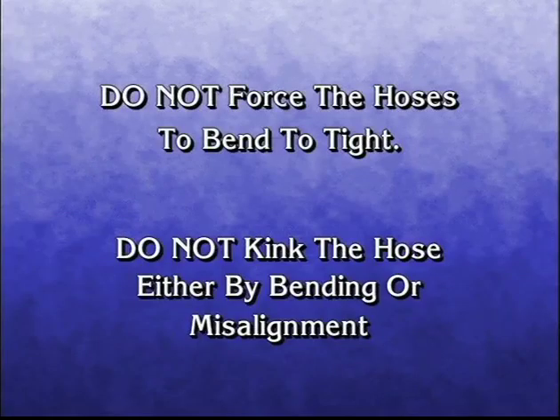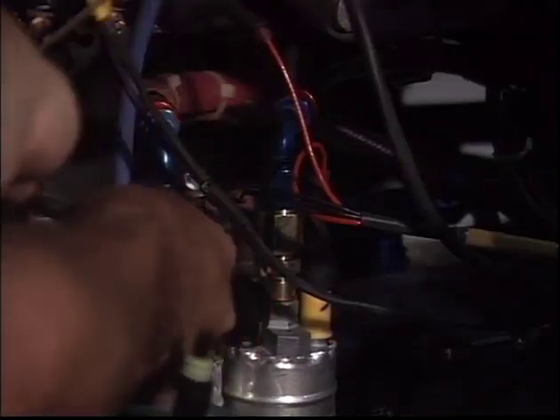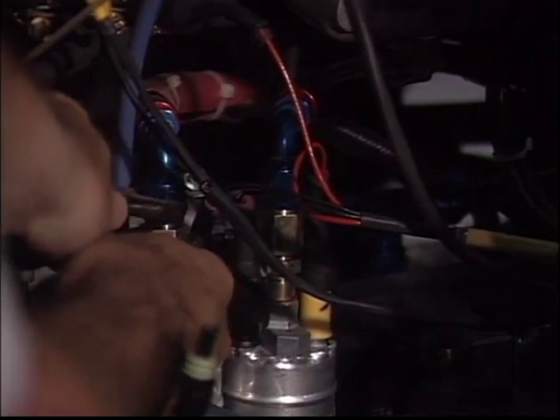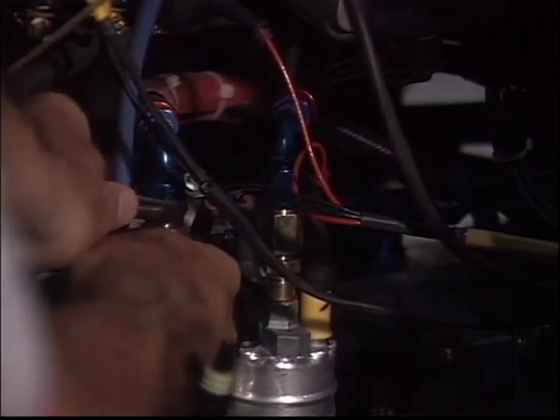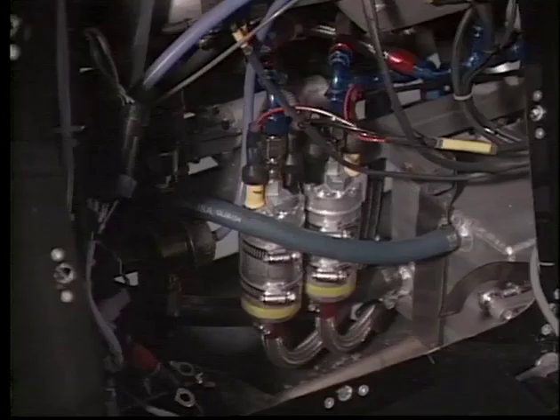Do not force the hoses to bend too tight. Do not kink the hose, either by bending too tight, by misalignment between the hose end and fittings on the short assemblies, or by getting the whole assembly into a helix on long assemblies. Check the tightness of all fuel hoses. Do not over-tighten the hose ends onto the adapter fittings. The seal is achieved by the design of the mating surfaces, not by muscle. If it leaks, it has probably been assembled incorrectly. Damage to the cone and seat can be caused by various mistakes on assembly, the most common of which are dirt and over-tightening.